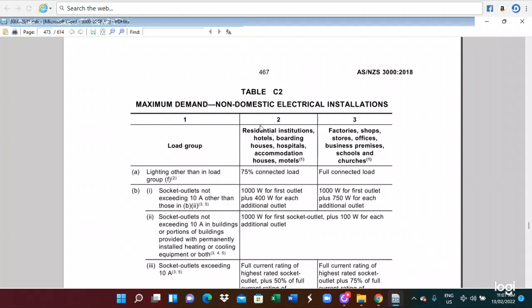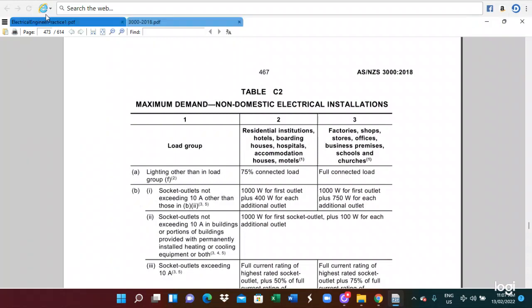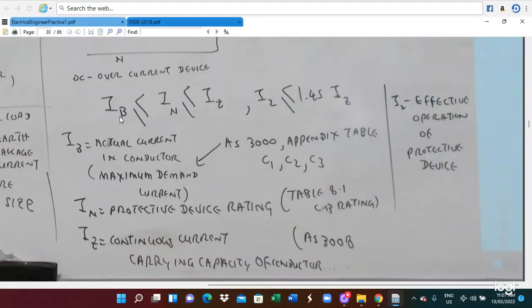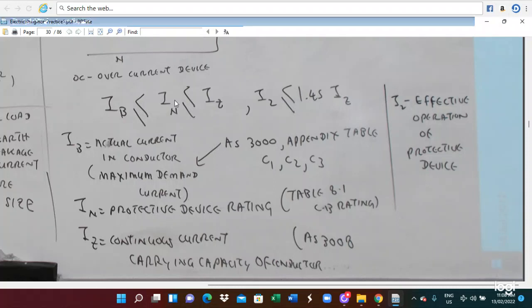Table 3: you calculate this area, look at your drawing, then you can determine how much volt ampere. So this is the electrical current you have to calculate. This current is IB. IB means depending on the maximum demand calculation, you can select the IB. IN means protective device rating. For the protective device rating you have to refer to Table 8.1, the circuit breaker rating.